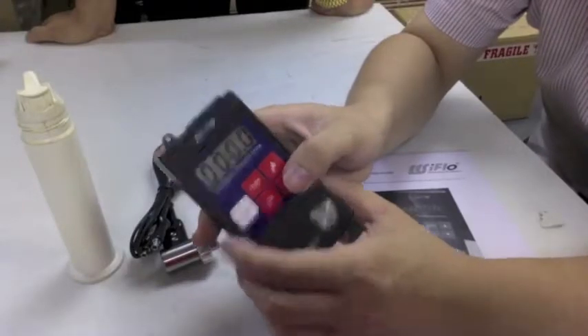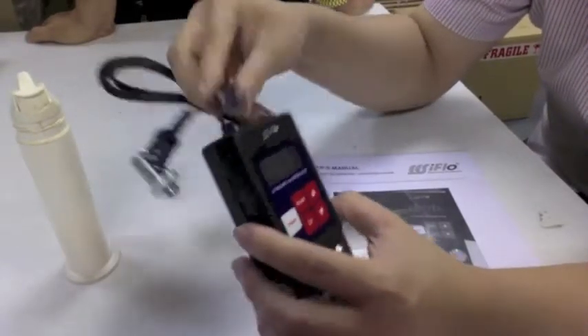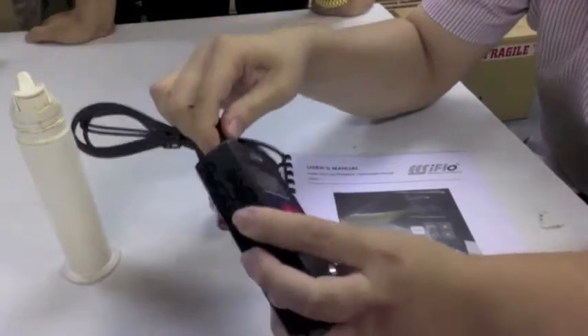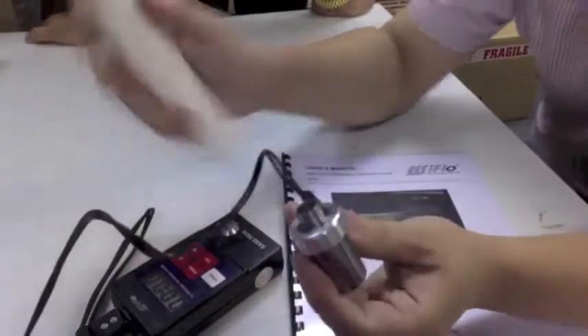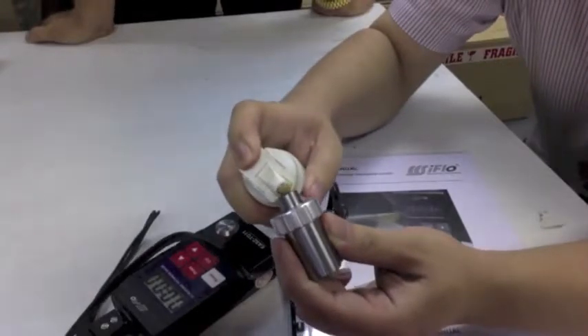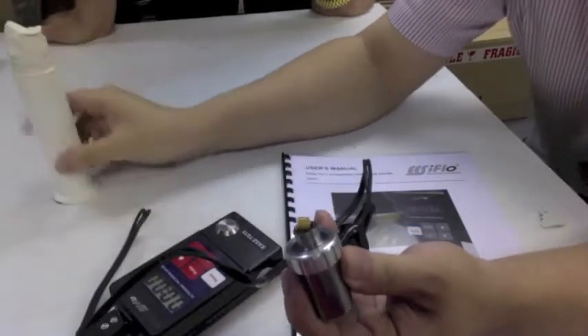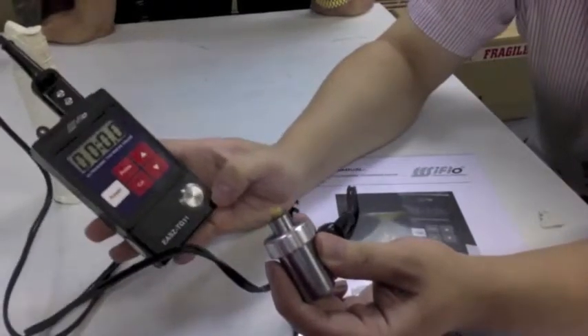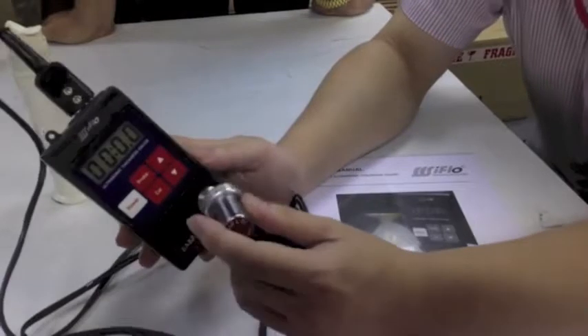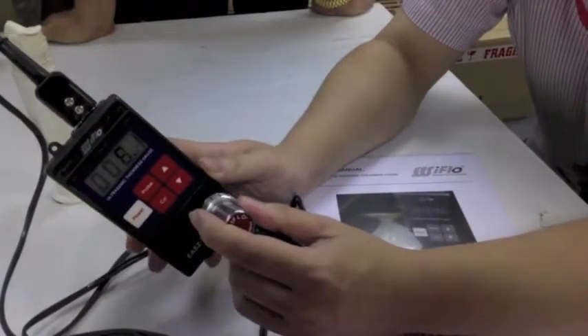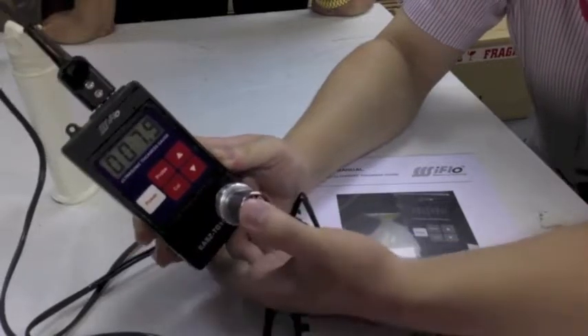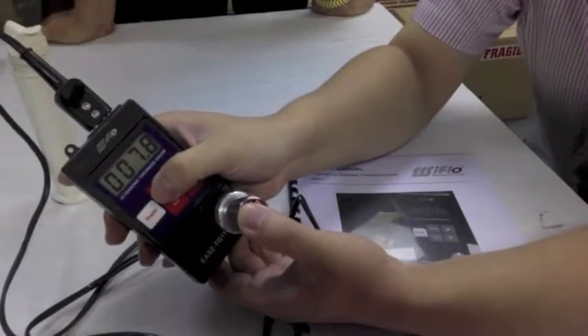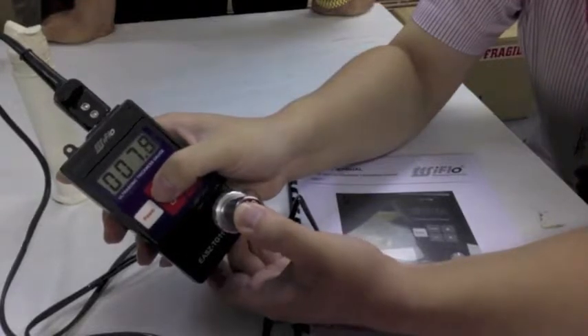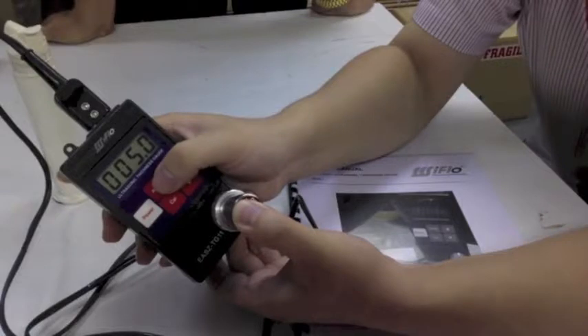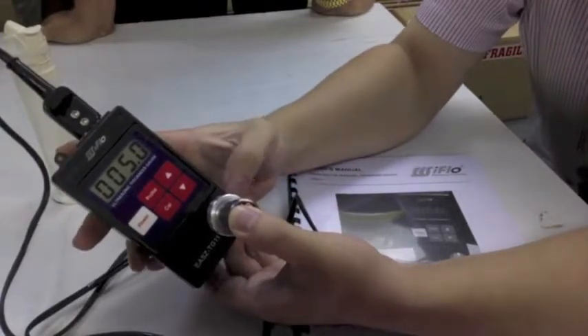When you are ready to take a measurement, simply take the probe connector and plug it into its appropriate sockets. If you are measuring mild steel, simply apply couplant to the probe head and use the test block. The test block is exactly 5mm mild steel. Press down firmly on the block, press the probe down firmly, and then press the probe button. Make sure that your reading corresponds to 5mm. After this, you are ready to take measurements.